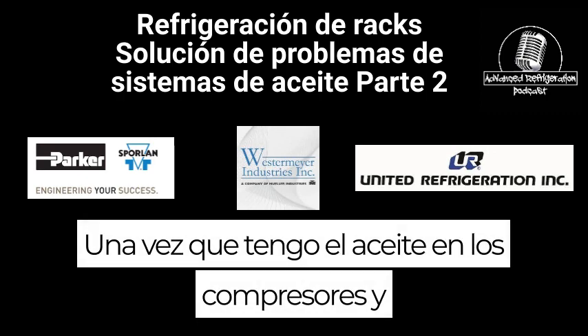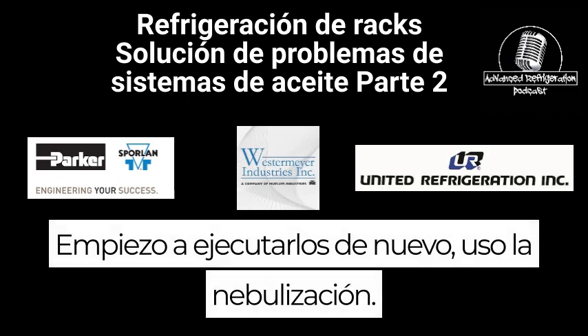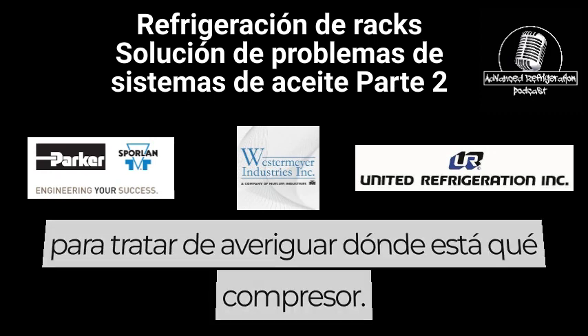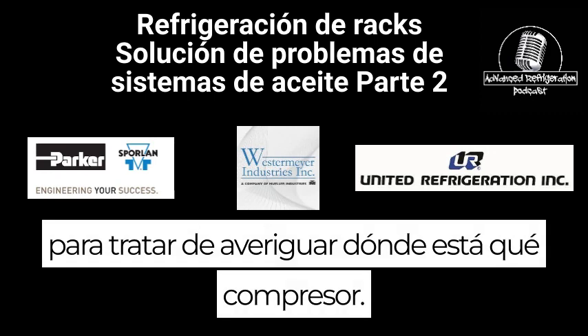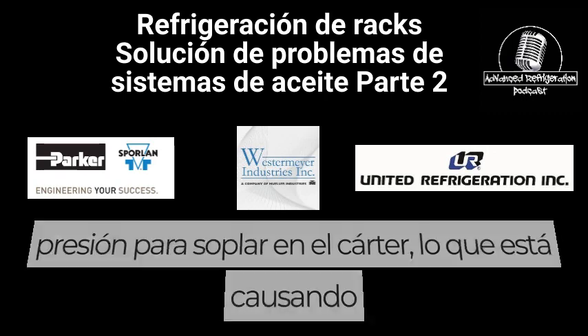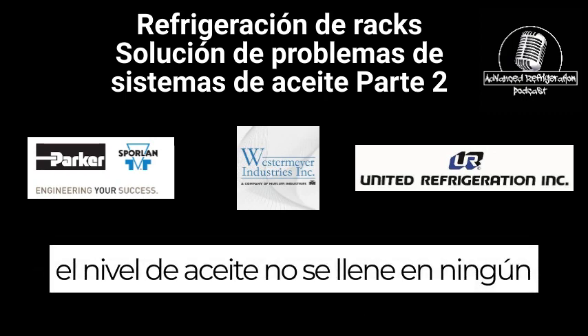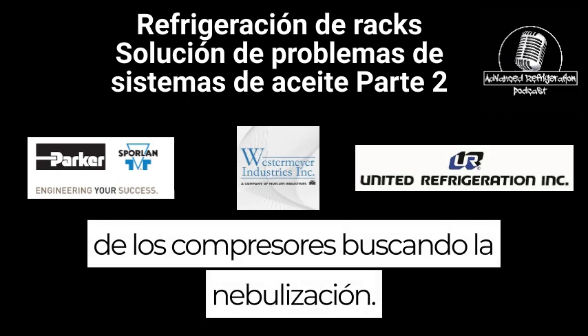Once I get the oil in the compressors and I start running them again, I use the misting to try to figure out which compressor is my culprit, the one that's causing the discharge pressure to blow into the crankcase, which is causing the oil level not to fill up on any of the compressors.